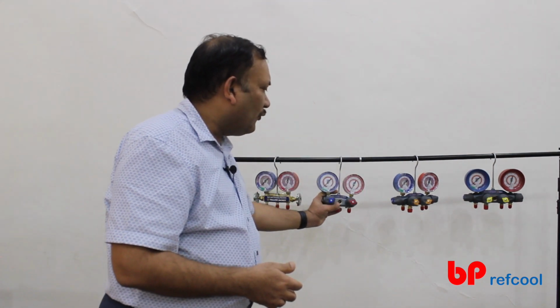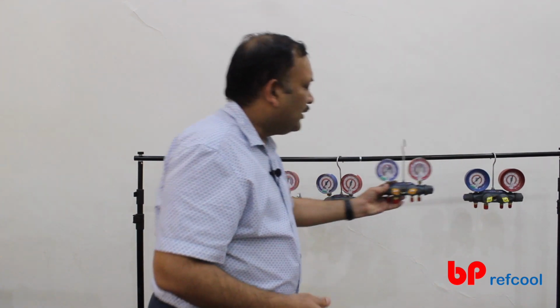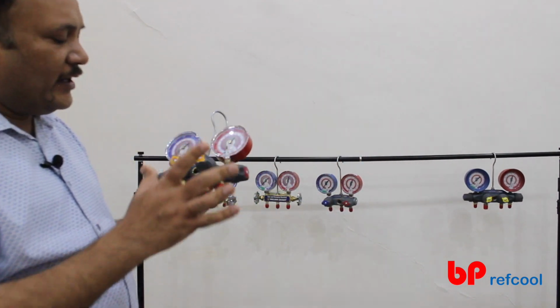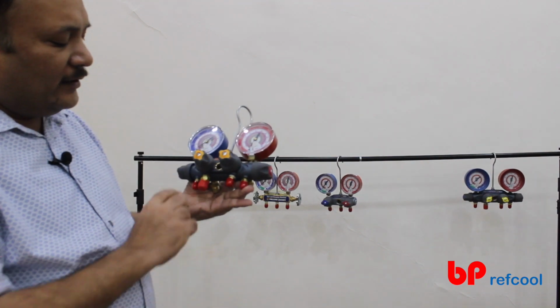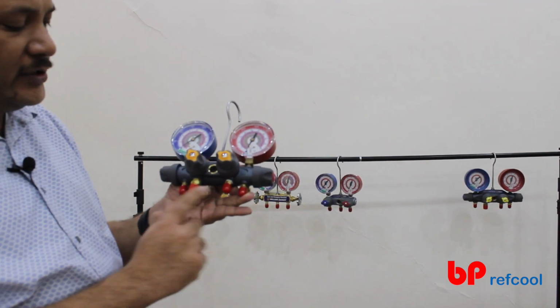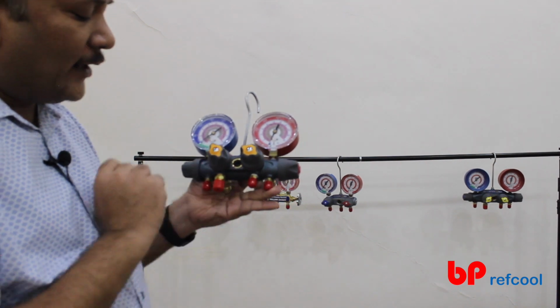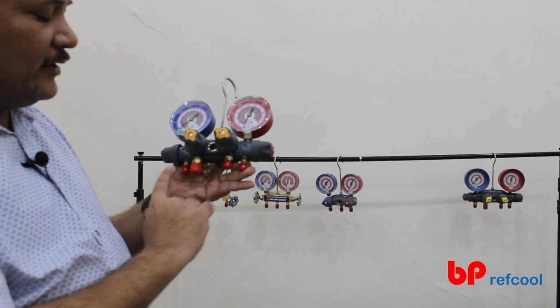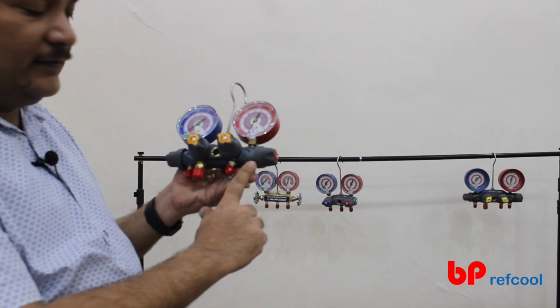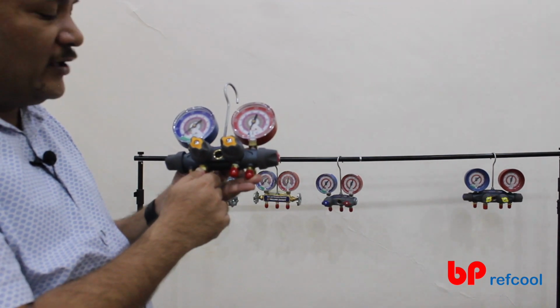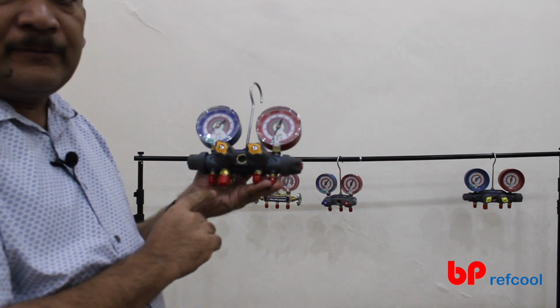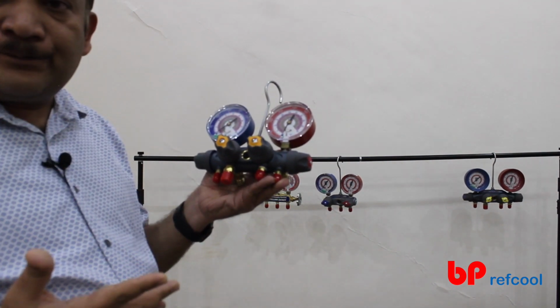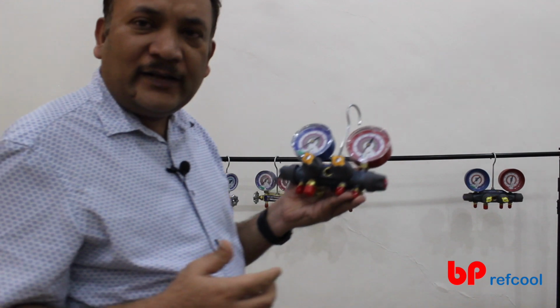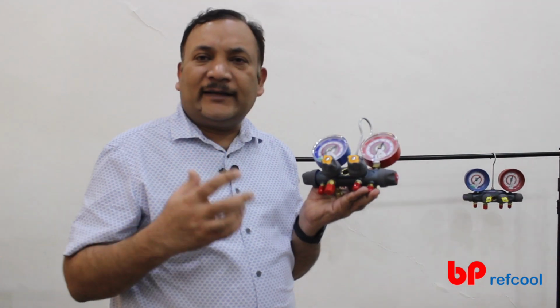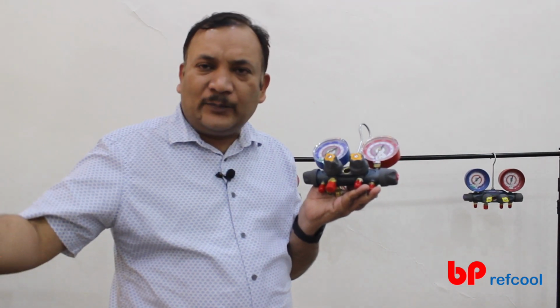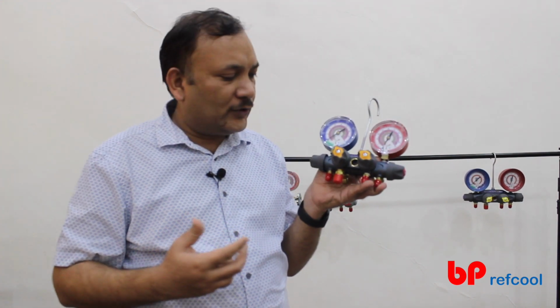Now we have a four-way manifold from Titan, so the Titan series. You can see in this four-way, as compared to two-way, we have 4 ports on the bottom. Of these 4 ports, 2 are the similar ones which you connect to the low side and to the high side, and then this is vacuum. Now vacuum in these cases is normally 3/8, so a higher size. In 3/8 it is easy for you to connect a larger dia hose to a vacuum pump so that you can vacuum the system faster.